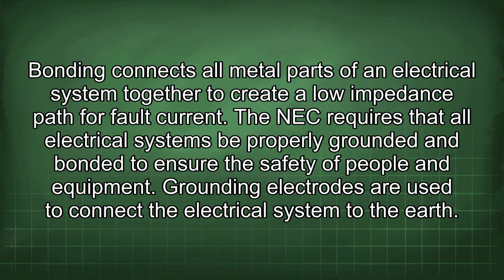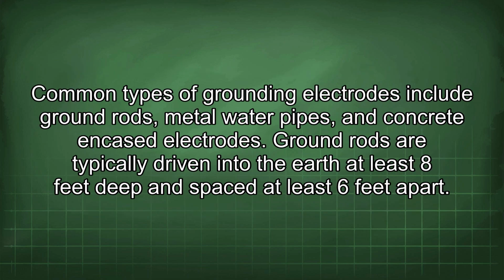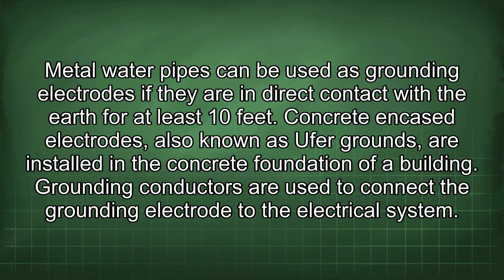Grounding electrodes are used to connect the electrical system to the earth. Common types of grounding electrodes include ground rods, metal water pipes, and concrete encased electrodes. Ground rods are typically driven into the earth at least 8 feet deep and spaced at least 6 feet apart. Metal water pipes can be used as grounding electrodes if they are in direct contact with the earth for at least 10 feet. Concrete encased electrodes, also known as Ufer grounds, are installed in the concrete foundation of a building.